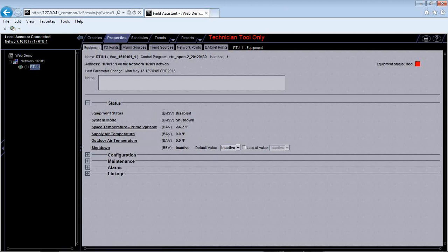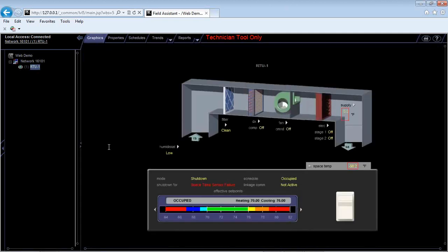This is just a general status view. If you wanted to see an update, most of this stuff can be seen on the graphic like we saw before. You can see I'm in shutdown mode, negative 56.2. And I have these red boxes around these items. If you ever see a red box, that means there's a problem with that portion of the controller, right? So I have a problem with my space temperature sensor. I have a problem with my supply temperature sensor. And you can see I'm actually saying I'm in shutdown mode for space temperature failure, okay? So we need to configure our unit so it can function properly and so we can get past these alarms or errors.